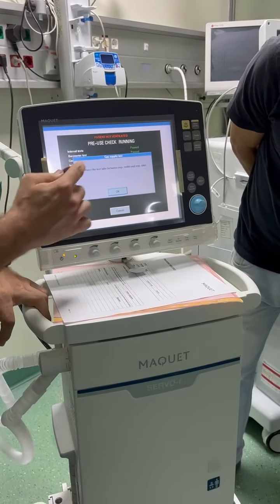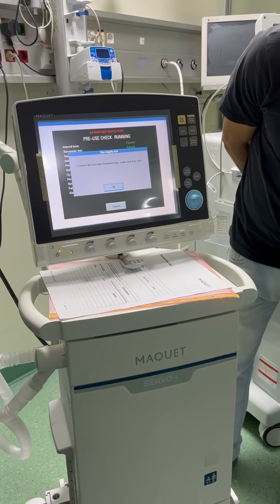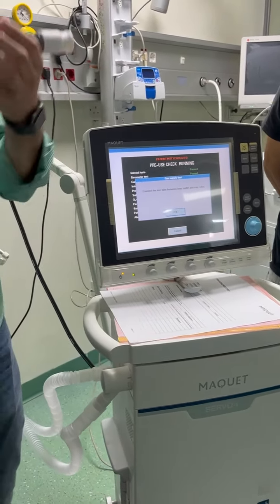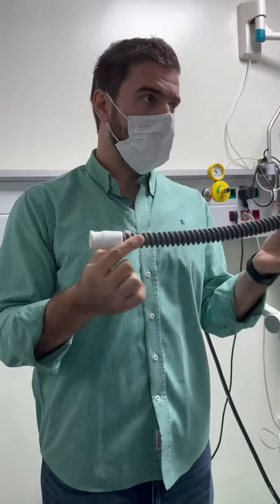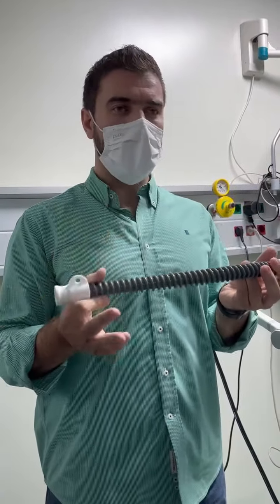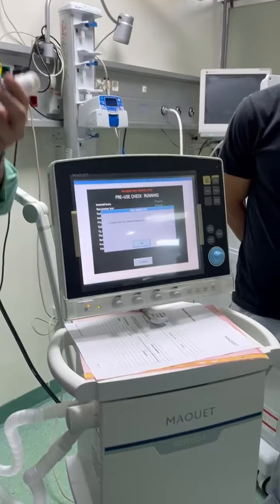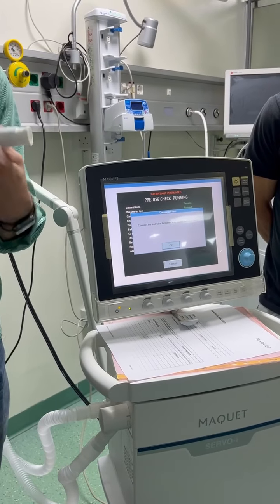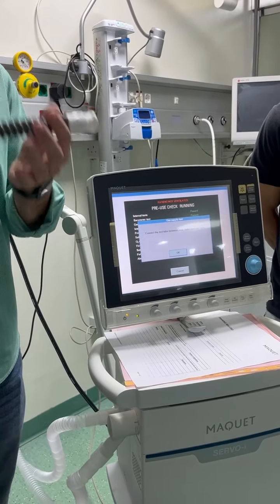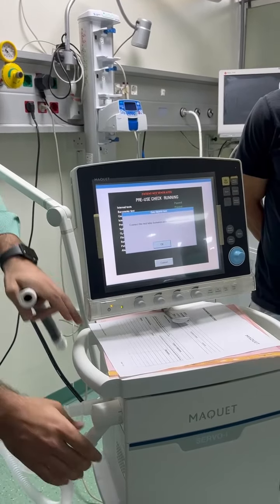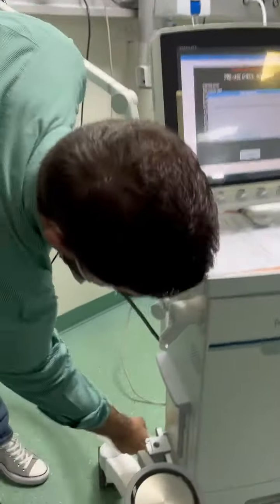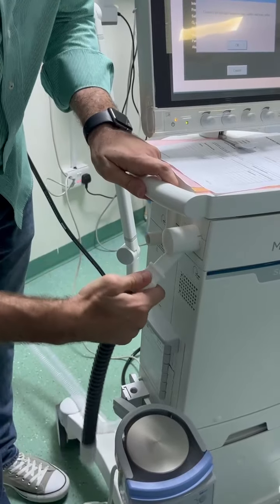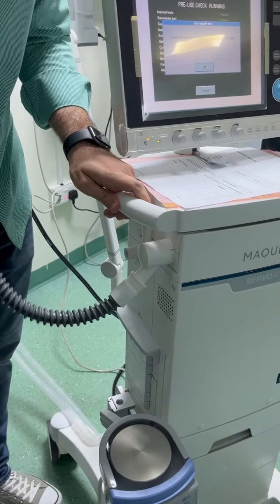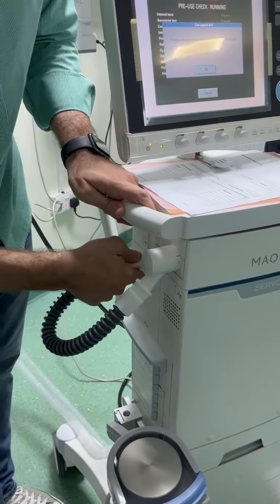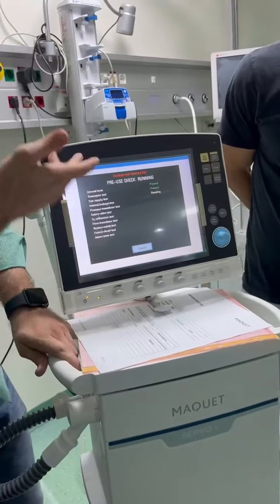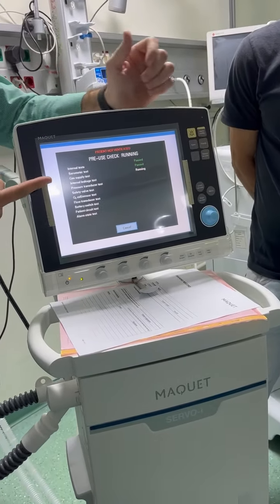So what it says now: connect the test tube between inspiratory outlet and expiratory. This is called the test tube. Every machine has a test tube. I prefer, I wish, not to lose it. However, if you lose it, I'll be happy because you have to buy again from us. But I prefer not to lose it. What to do? Very simple. Just connect it between inspiratory and expiratory, and press OK. Then it will go to check the ventilator in some steps.